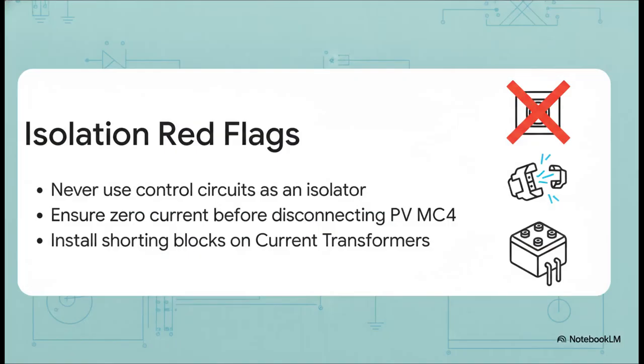While you're isolating, you need to watch out for a few massive red flags highlighted in the safety guide. First off, never, ever use control circuits or functional switches, like your standard light switches, as isolators. They are simply not rated for it. Second, when dealing with solar, if you pull an MC4 connector while current is still flowing, you are going to draw a massive, dangerous arc. You always prove zero current first. And third, if you disconnect current transformers from their low impedance circuit, they can produce a lethal high voltage. Always install shorting blocks, links, or bridges whenever a CT circuit is interrupted.